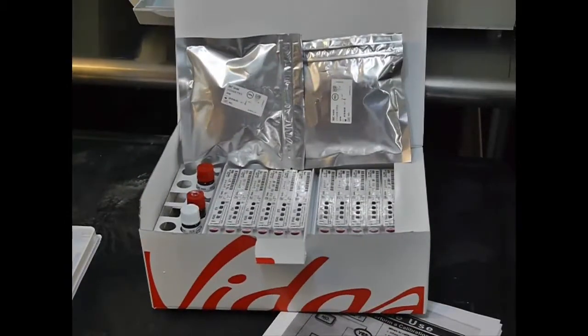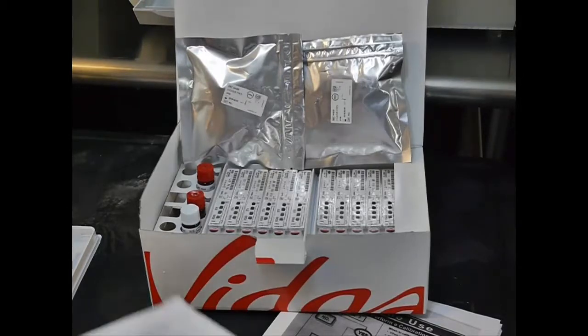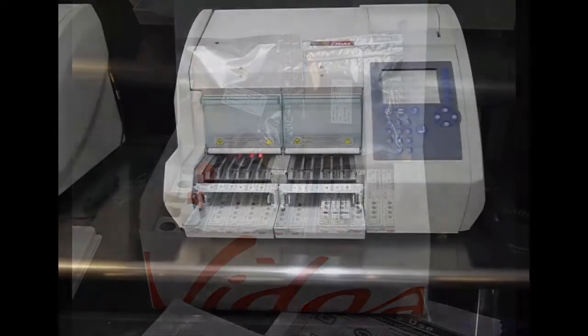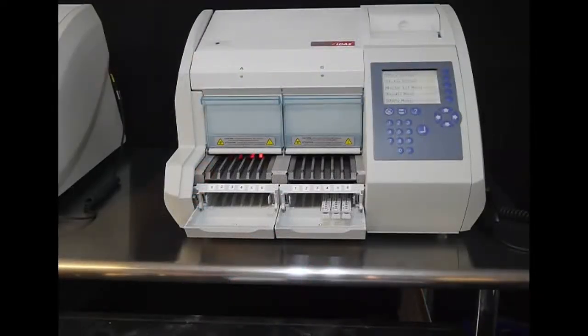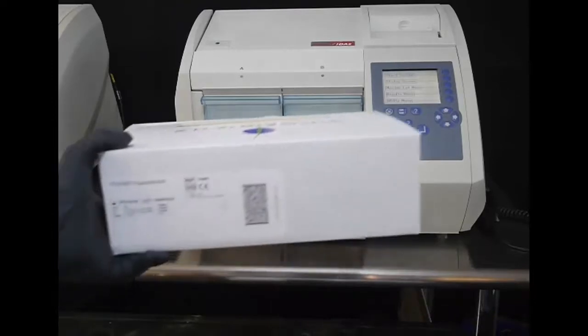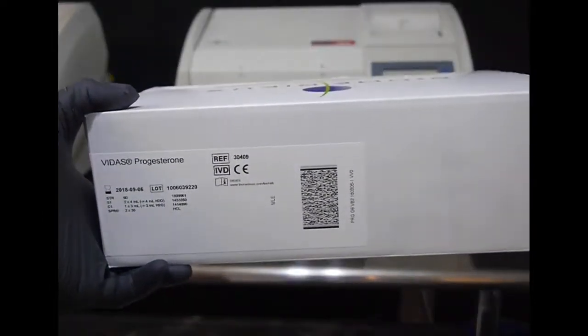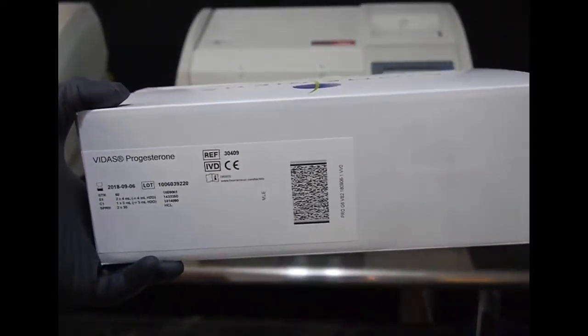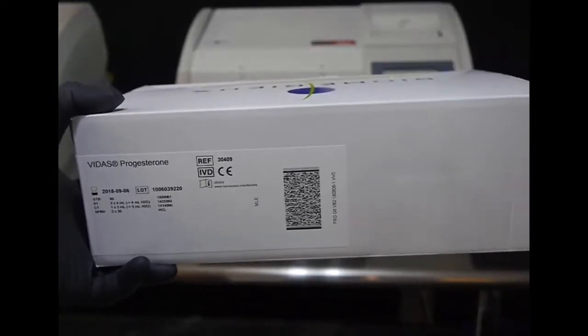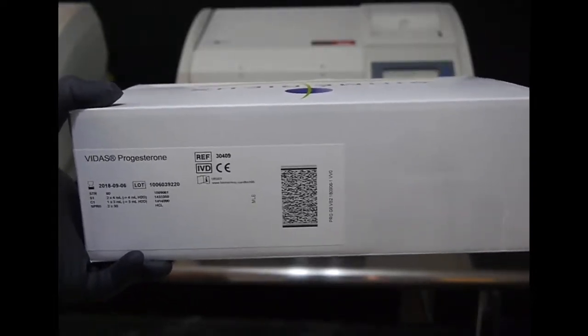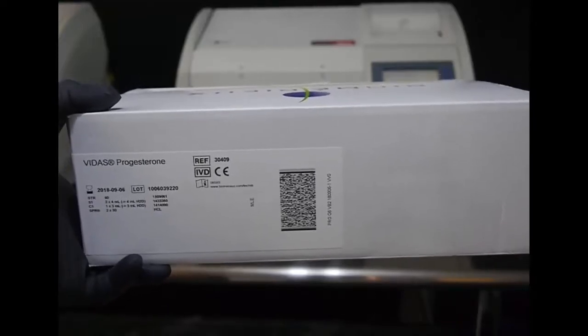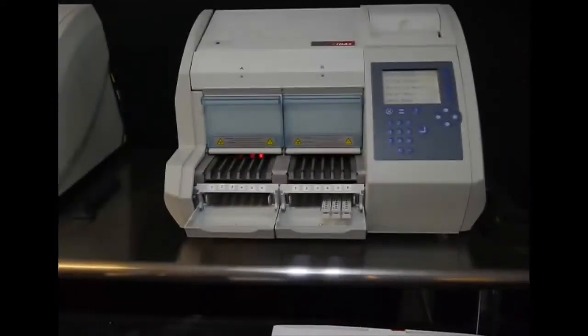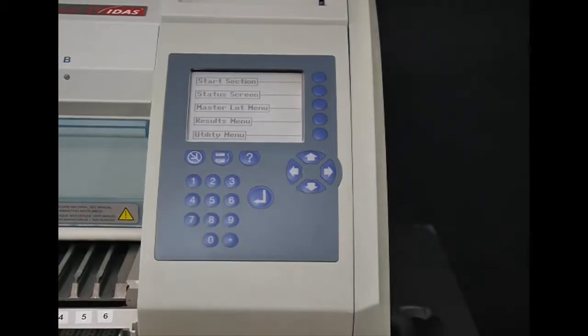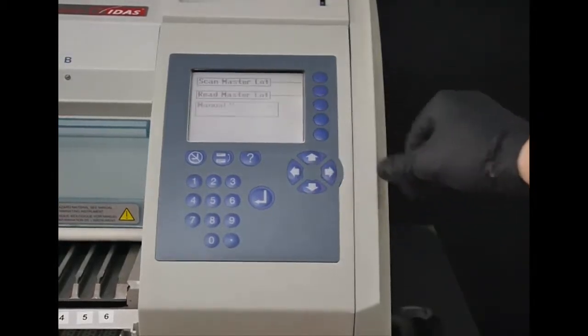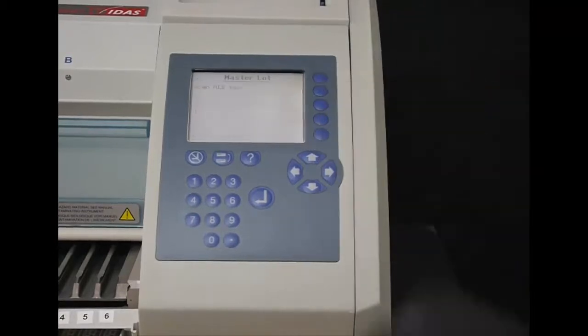Once reconstituted, it is important to return all elements of your kit to the fridge to be stored at 2 to 8 degrees Celsius. The first thing you should do upon receiving a new kit is to scan the MLE barcode found on the side of the box into the machine using the barcode scanner. Each and every new kit will need to be calibrated, or once every 2 weeks with the same kit. To do this, we will go to the main menu, select Master Lot menu, and scan Master Lot.